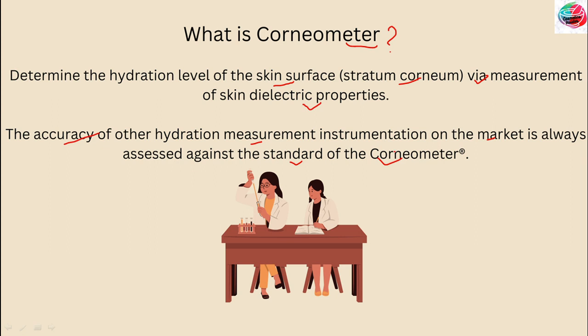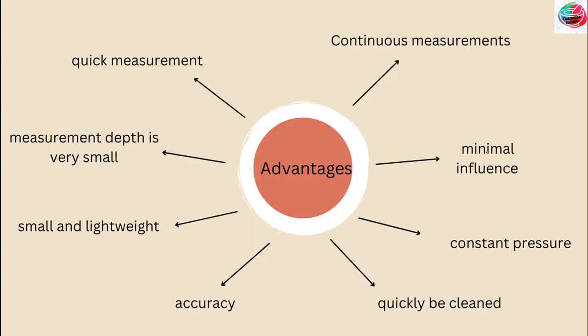The Corneometer is considered the standard for other skin hydration measurement instruments available in the market. Among its advantages: the probe allows very quick measurement — just one second — which helps avoid occlusion. Continuous measurements over a longer period can be optimally performed. Substances on the skin such as salts or residues of topically applied products have only minimal influence, due to the capacitance measurement principle.